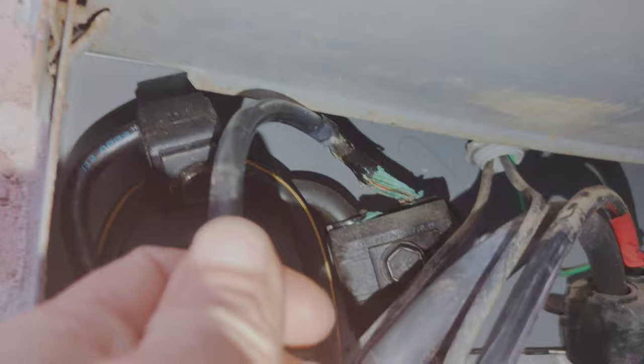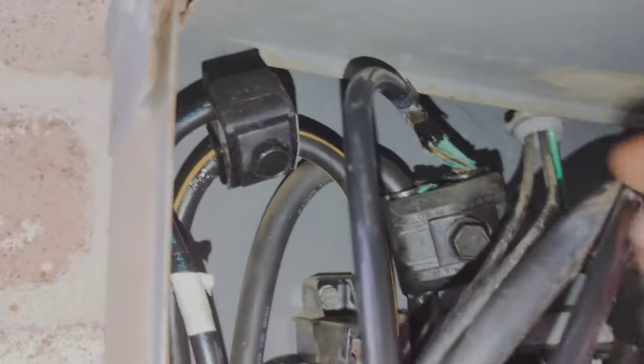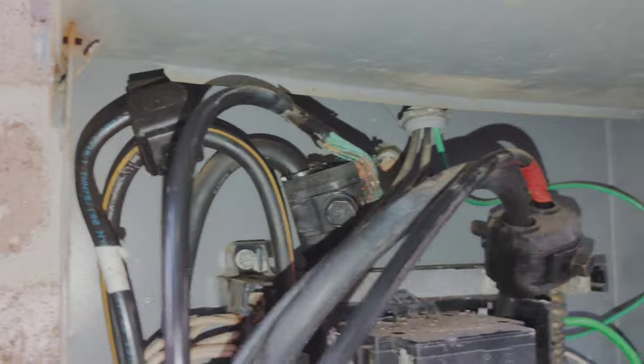While my power was off and I had a generator running, I noticed in my breaker box that the wires from the solar panel system were not tight. This wire had been melting and overheating because the connector wasn't even tight — I could loosen it with my fingertips. The other connectors were tight, but this one wasn't. That's exactly why it was overheating. I don't know who installed this but they should be ashamed of themselves. This by no standards meets what an electrician should be doing.